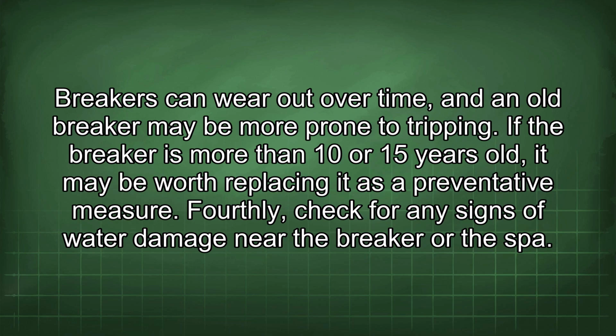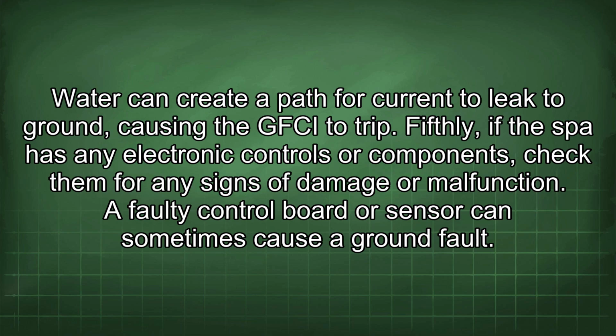Breakers can wear out over time, and an old breaker may be more prone to tripping. If the breaker is more than 10 or 15 years old, it may be worth replacing it as a preventative measure. Fourthly, check for any signs of water damage near the breaker or the spa. Water can create a path for current to leak to ground, causing the GFCI to trip.